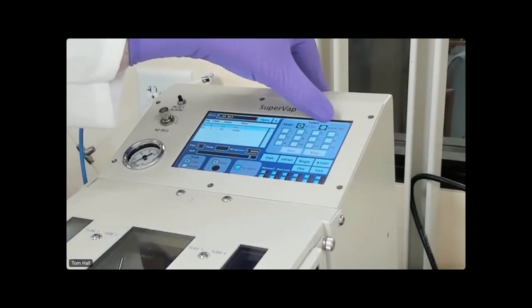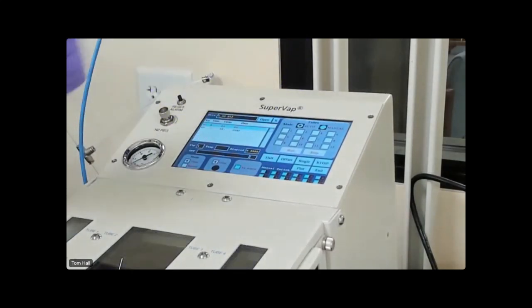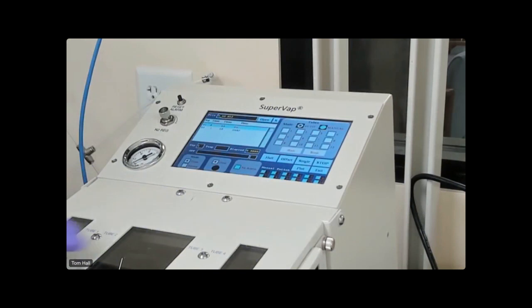You can also run the system in manual mode. Auto mode means you have these pre-programmed lines. If you do it manually, then you can regulate each of the positions individually. However, it will operate at one temperature, and you can just pull it out. You can sometimes use manual mode if your sample has a different color or some other material in it that the infrared beam gets confused by. Then you can run it in manual mode and blow it down as low as you want yourself. So it's basically just human control at that point versus control by the evaporator.